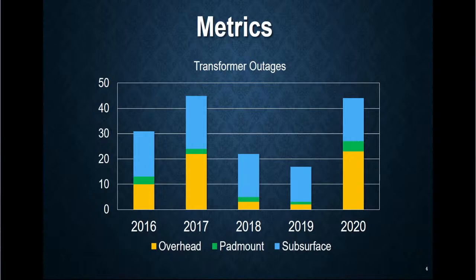Pad-mount transformers, shown in green, are usually very reliable with the lowest number of outages. Subsurface transformers fail because they typically reside in a harsh environment below ground, subject to water and debris intrusion.